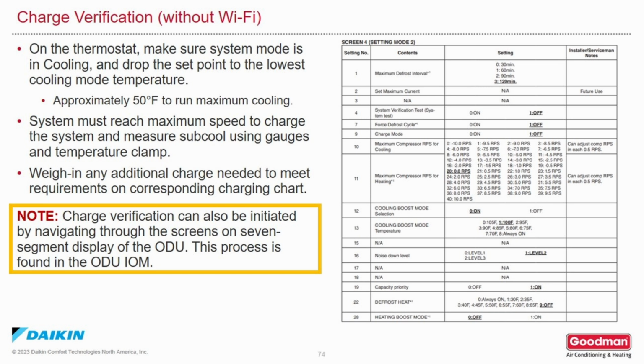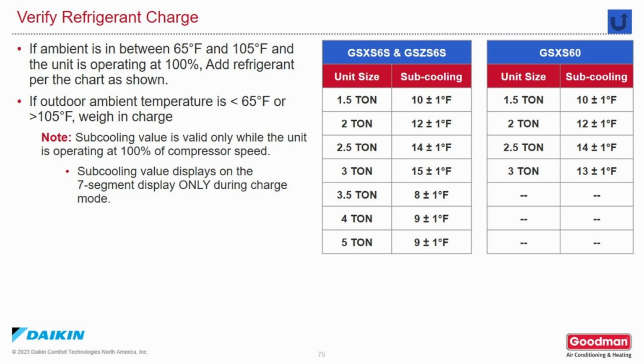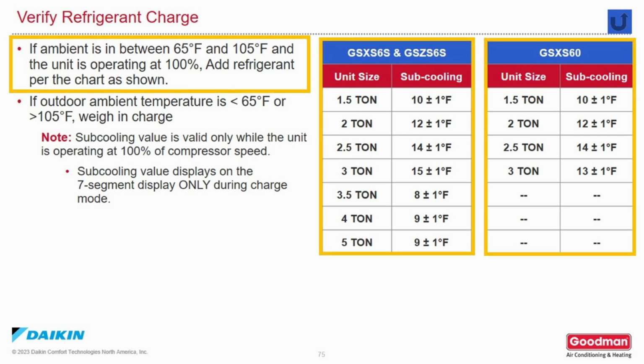Charge verification can be initiated by navigating through the screens on the display of the outdoor unit. Instructions for this process can also be found in the outdoor unit IOM. To verify the refrigerant charge, if the ambient temperature is between 65 degrees Fahrenheit and 105 degrees Fahrenheit, and the unit is operating at 100% capacity, add refrigerant to match the chart that's shown on the right, which can be found in the outdoor unit IOM.